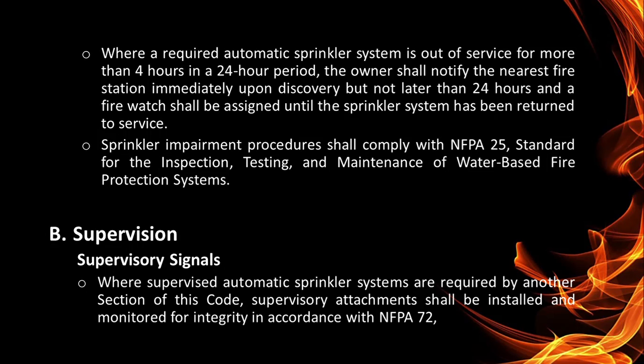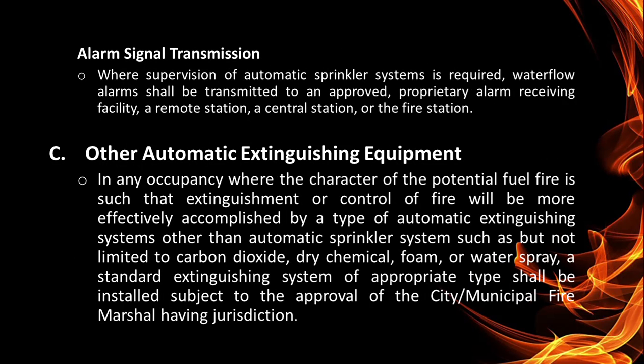Next is supervision. Supervisory signals, where supervised automatic sprinkler systems are required by another section of this code. Supervisory attachments shall be installed and monitored for integrity in accordance with NFPA 72. Alarm signal transmission: where supervision of automatic sprinkler system is required, water flow alarm shall be transmitted to an approved proprietary alarm receiving facility, a remote station, a central station, or the fire station.